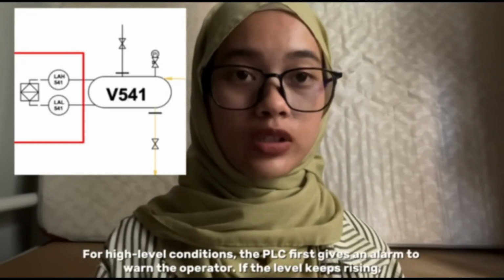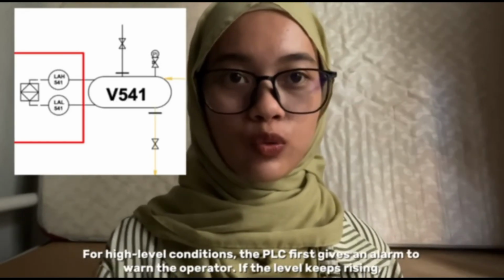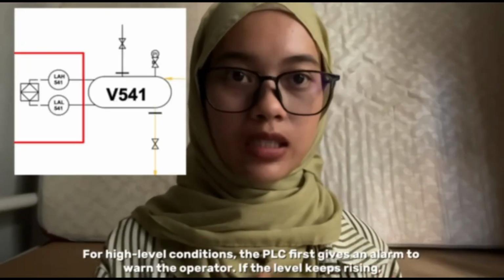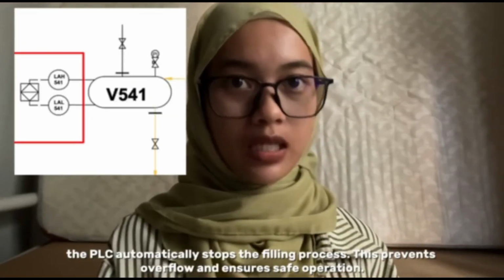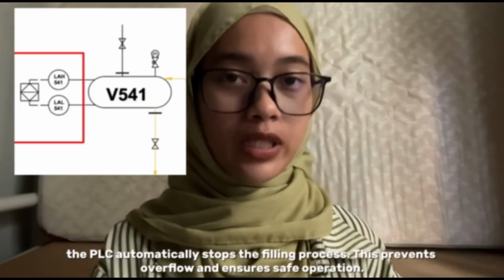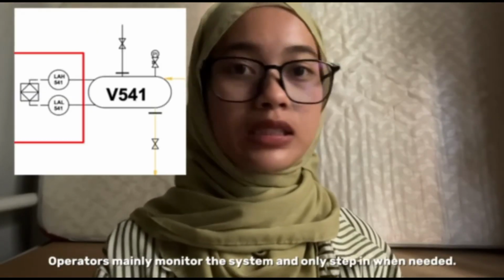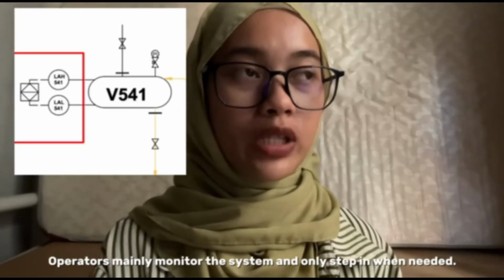For high level conditions, the PLC first gives an alarm to warn the operator. If the level keeps rising, the PLC automatically stops the filling process. This prevents overflow and ensures safe operation. Operators mainly monitor the system and only step in when it's needed.